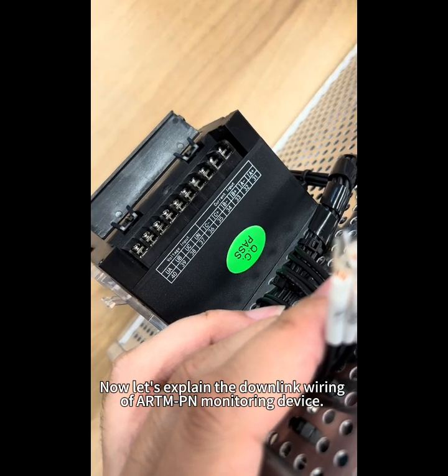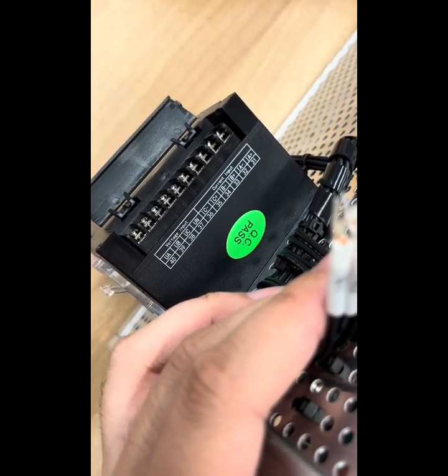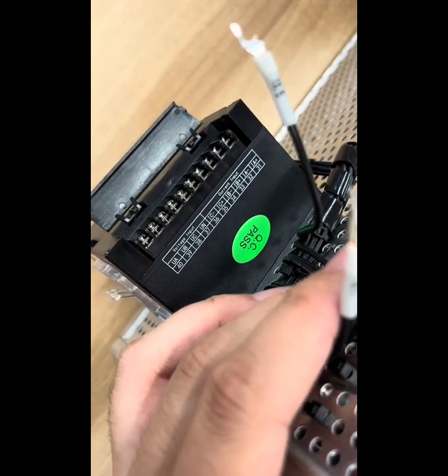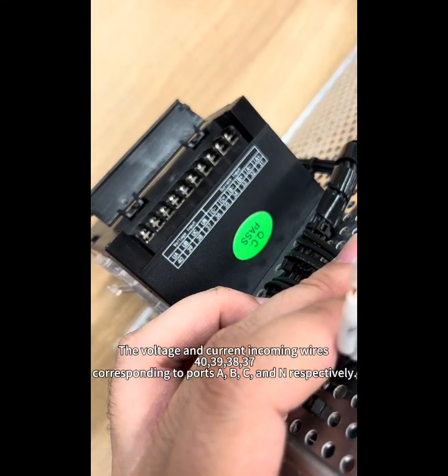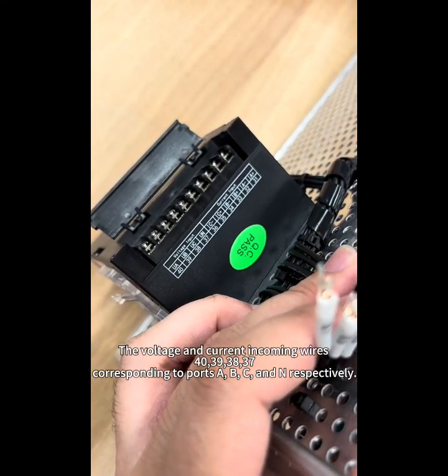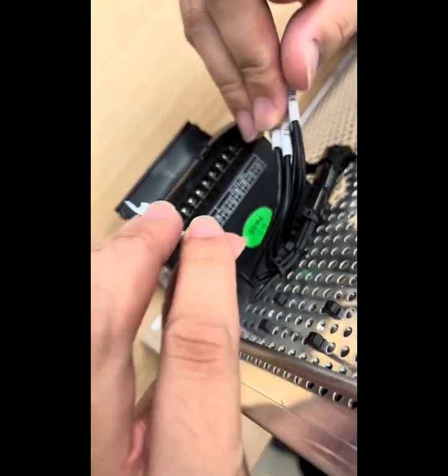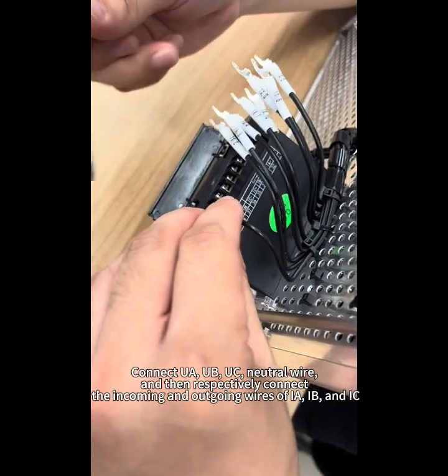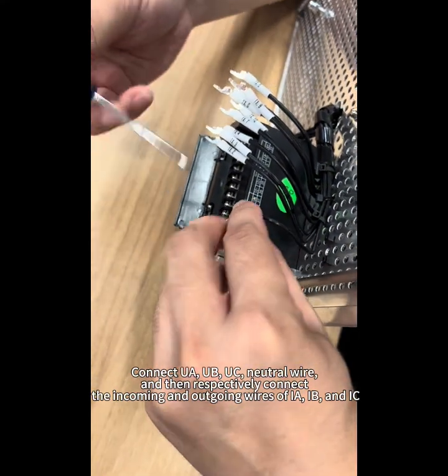Now let's explain the downlink wiring of the ARTM-PN monitoring device. The voltage and current incoming wires use ports 40, 39, 38, and 37, corresponding to phases A, B, C, and N respectively. Connect U-A, U-B, U-C, and the Neutral wire. Then respectively connect the incoming and outgoing wires of I-A, I-B, and I-C.